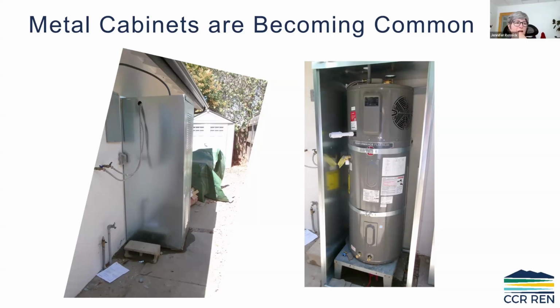When these units first came online, the code and manufacturers would tell people minimum 750 cubic feet of volume in the room, maybe 1,000. Now manufacturers are saying 400 to 450 on their installation instructions, already cut roughly in half. The code's mandatory measure is the capacity of the heat pump times 100 cubic feet. With most units around 4.2 kBTU, that works out to about 420 cubic feet. But our rule of thumb for architects is to do 450 at the minimum.